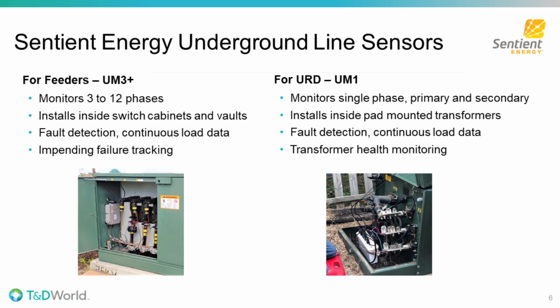For UM1, there is no amperage necessary at all because the power supply of this device is getting the power directly from the secondary 120/240, the hot legs of the transformer. So as a result, no matter what the amperage is, the device is always powered 24/7 and doesn't depend on harvesting.